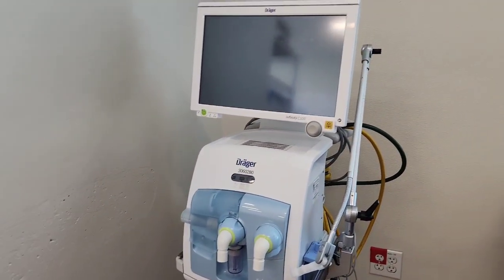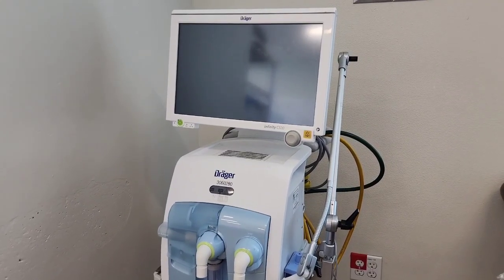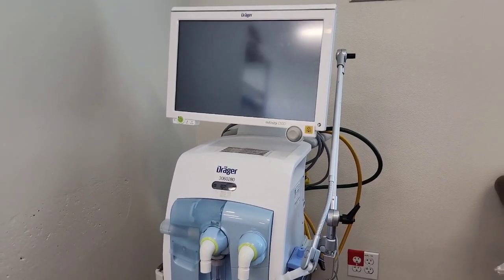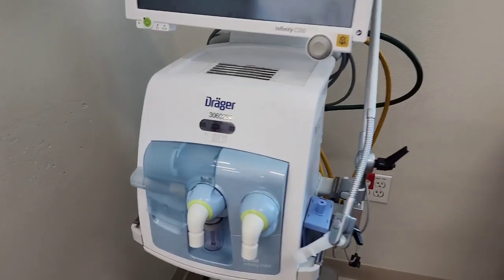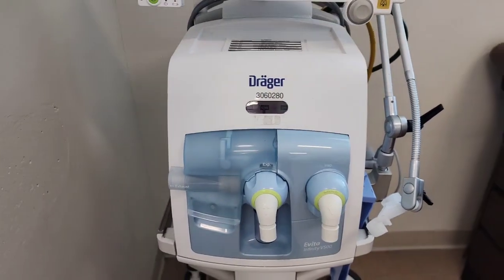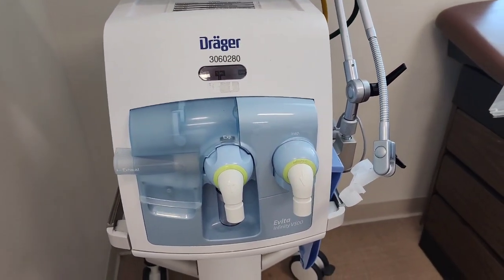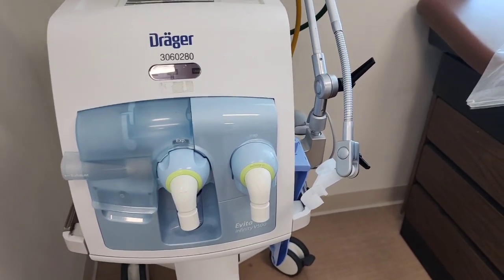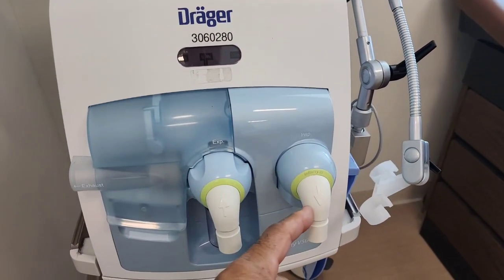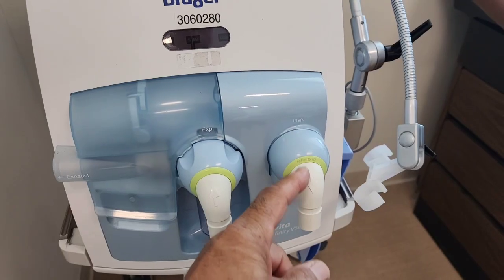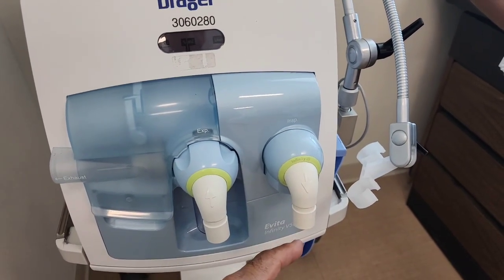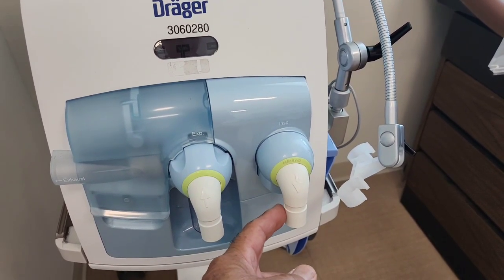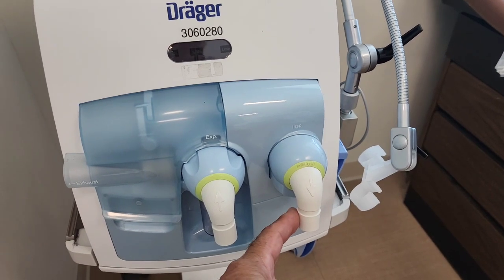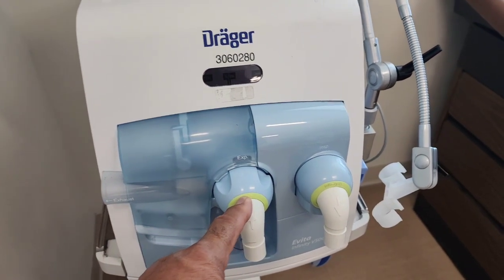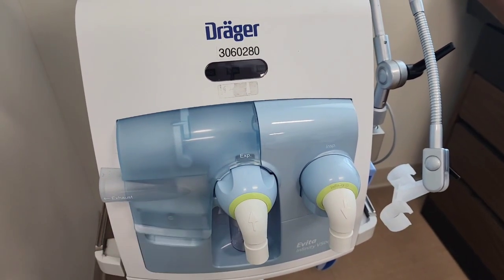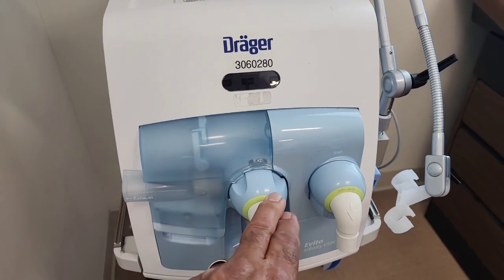Today we're going to look at the Draeger ventilator. And I'm going to get a little bit closer. So the Draeger here has two connections in the front. One of them is inspiratory. It says inspiratory up there. That's to the patient. This is where we will connect the bacteria filter right here. This one here is expiratory, in other words, exhalation coming back to the ventilator.